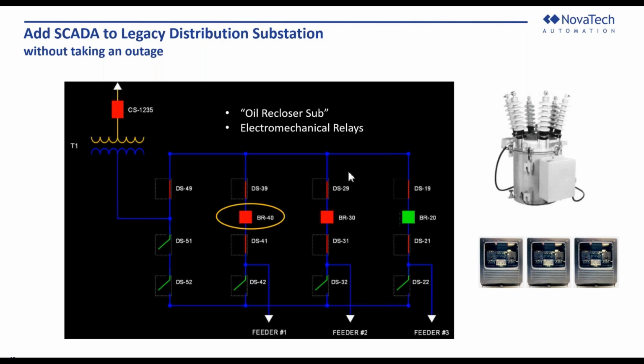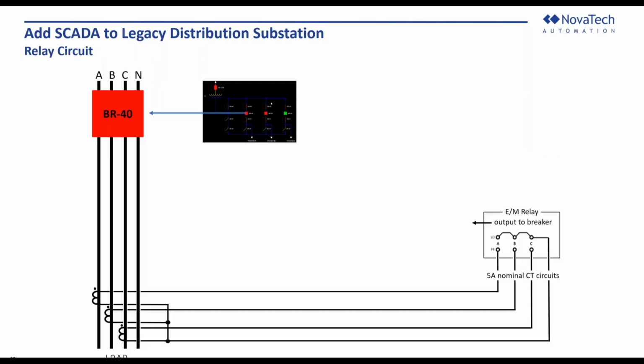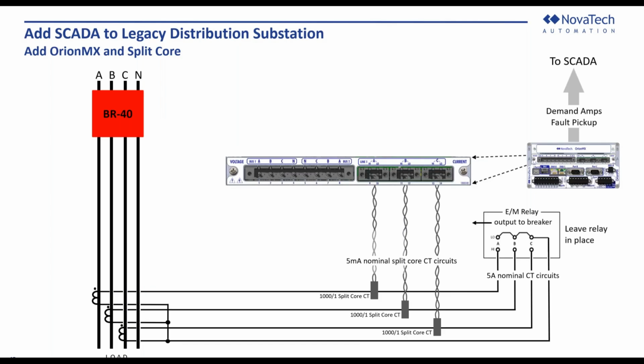So we'll look at that circuit there, breaker 40, and the electromechanical relay, hypothetically, that could be in that substation. We could say it could be connected in there like that. We have 5 amp nominal CT circuits coming into the electromechanical relay. Of course, there'd be an output to the breaker. So the first thing we would do is add in the meter card with the Orion. And there you see the split core CTs, 1000 to 1, converting the 5 amp nominal to 5 milliamp. And that is a very simple, straightforward way of adding automation. Of course, you don't have to take an outage to put those split core CTs on there.